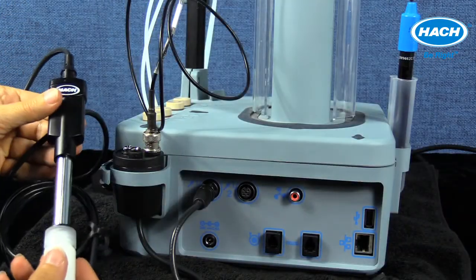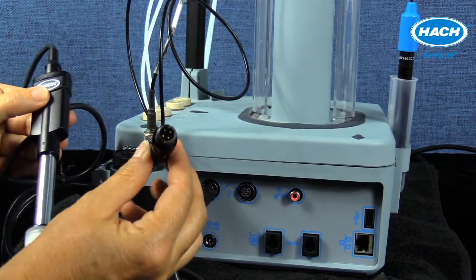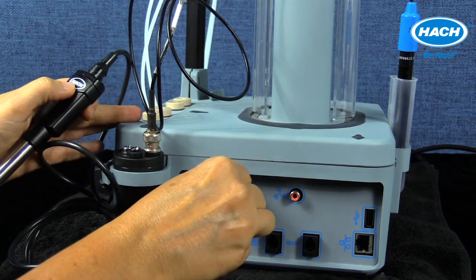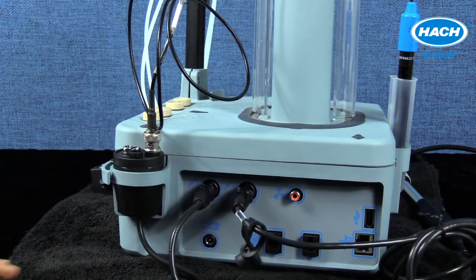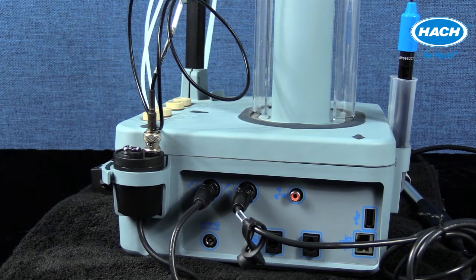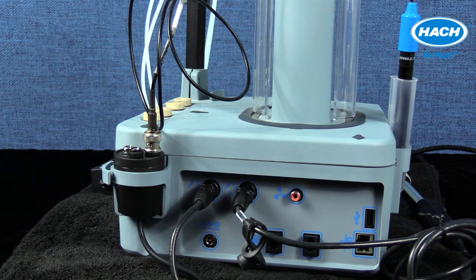The IntelliCal electrode sensor is received with the purchase of the application kit, and the model received depends on the kit purchased and titration to be performed. The electrode sensor, with its M12 digital connector, is connected into the back of the titrator in either the sensor 1 or sensor 2 connection ports. In this example, sensor port 2 is used. The titration software will recognize the digital electrode sensors connected, and is also able to track and prompt electrode maintenance such as cleaning, calibration, and replacement.